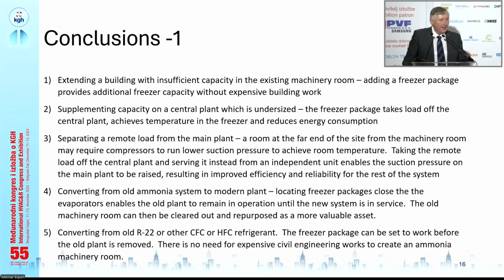benefit. If you have a building with a room very far away, for example, a freezer at the end of a long line, and the entire central plant is running at a low suction pressure to serve that one room, putting that one room onto a remote standalone unit will enable an energy benefit in the rest of the system as well. So there's actually a second benefit that can be gained. And if you convert from old ammonia plant to modern ammonia plant, putting the freezer packages close to the evaporators will reduce the suction line losses and improve the efficiency that way as well.